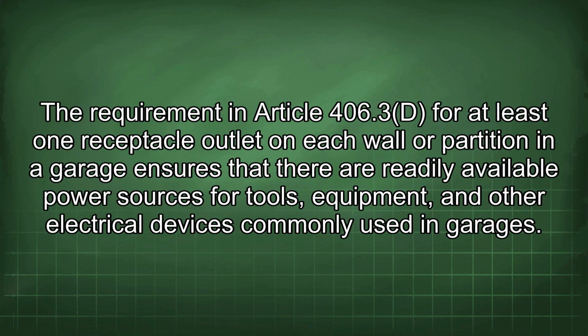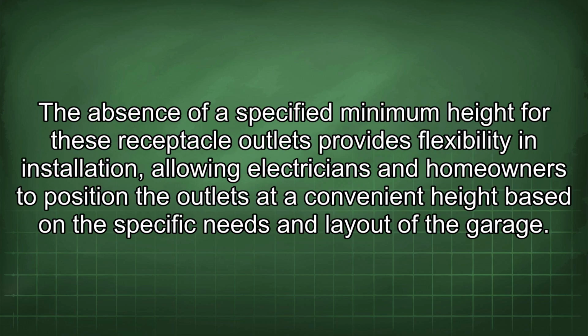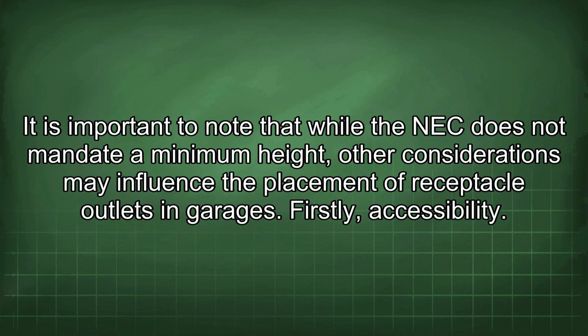The requirement in Article 406.3d for at least one receptacle outlet on each wall or partition in a garage ensures that there are readily available power sources for tools, equipment, and other electrical devices commonly used in garages. The absence of a specified minimum height for these receptacle outlets provides flexibility in installation, allowing electricians and homeowners to position the outlets at a convenient height based on the specific needs and layout of the garage. It is important to note that while the NEC does not mandate a minimum height, other considerations may influence the placement of receptacle outlets in garages.